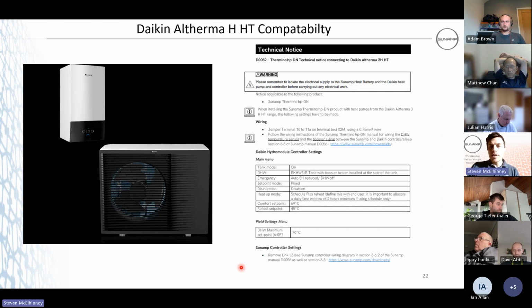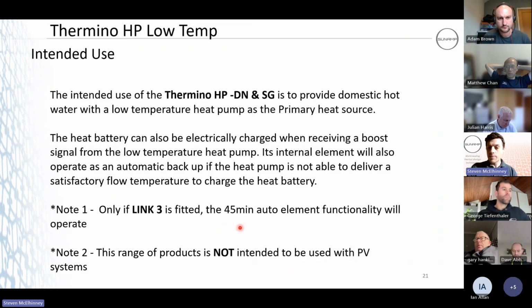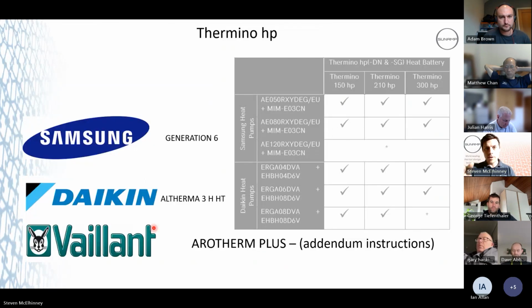We can fit it with the high temperature Daikin, the HHT. So just one thing to bear in mind, if the heat pump's able to achieve that 65-degree flow temperature, like they claim, you can remove link 3, and that will disable that 45-minute time delay. So link 3 in this case has got different functionality. It enables that element backup, or it disables it, for these units.